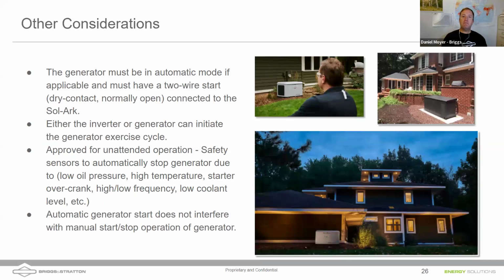So keep in mind some other considerations here as well. You have to, and this can be done inside of our generators at least, have it set in automatic mode. Additionally, you need to change the auto mains detect as well, which I was referring to earlier. It does have to be in the automatic mode for that 2-wire signal to be able to start up that generator. We talked about how either the inverter or the generator can initiate the exercise cycle. I'd say leave it up to the generator.